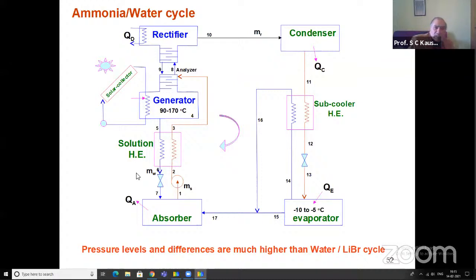So next is the ammonia water case. For the ammonia water cycle, the condenser, evaporator and absorber are the same, but for the generator, because along with the ammonia vapors some water vapors are also evolved, we use a rectifier, which is nothing but a fractionating distillation column, which can condense the water vapors through this analyzer, and the water vapors after being condensed go back to the generator.